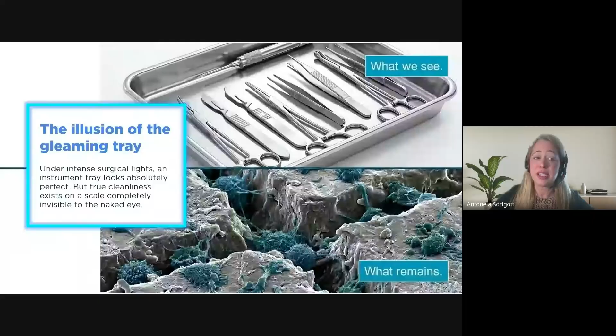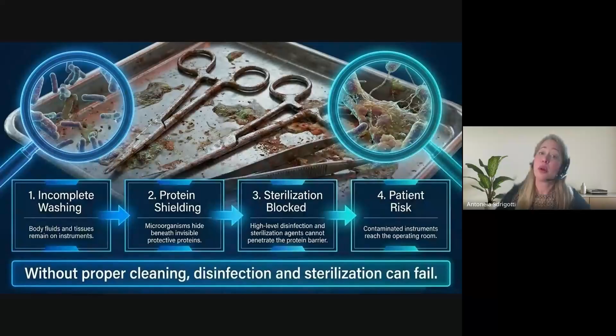So what happens? Incomplete washing leaves body fluids and tissues on the instruments, which will provoke protein shielding. Microorganisms hide beneath these invisible protective proteins. This will mean that sterilization will be blocked. High-level disinfection and sterilization agents cannot penetrate this protein barrier. As a consequence, this will result in patient risk because contaminated instruments reach the operating room. So without proper cleaning, disinfection and sterilization can fail.